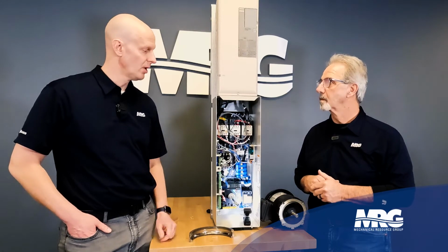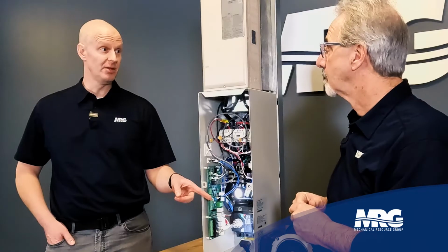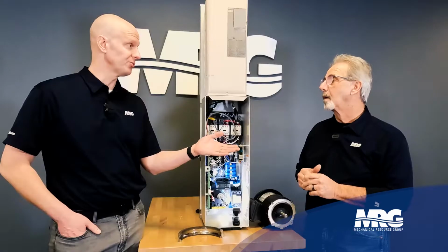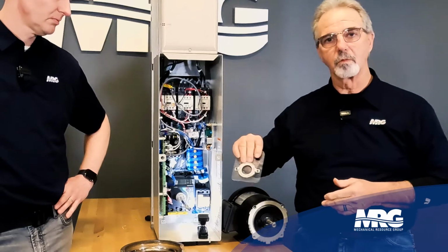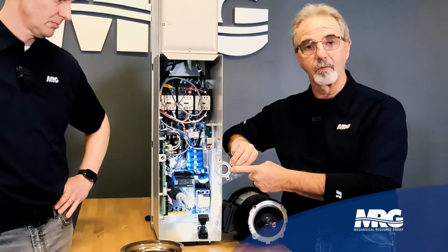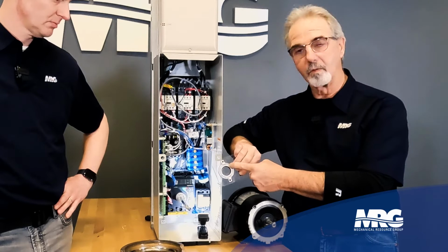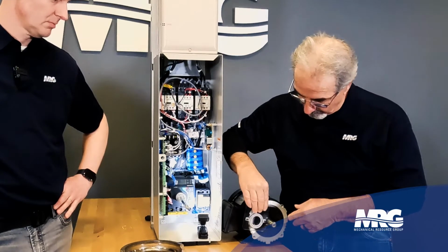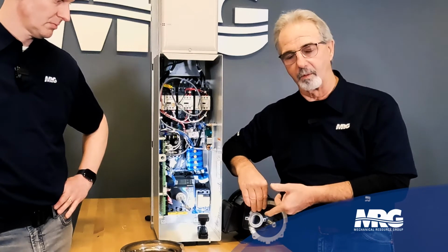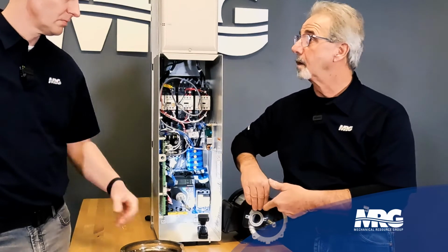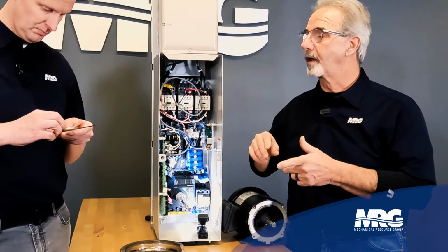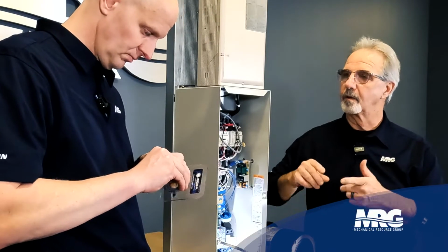Okay. So ceramic bearings are still a solution? It's still viable. What's the difference between a grounding ring and ceramic bearings? A grounding ring gives the least path of resistance for that voltage to find ground. A grounding ring is much like what you see here. It attaches to the motor frame, and there are carbon fiber brushes on the inside. If this ring was sized for this motor, it'd be much smaller, but it makes 360-degree contact on the shaft. The ring is grounded, so it's less resistance than the bearings are to get to ground.